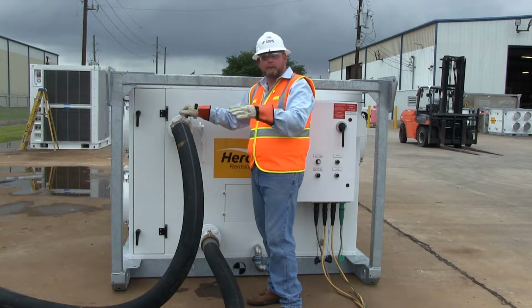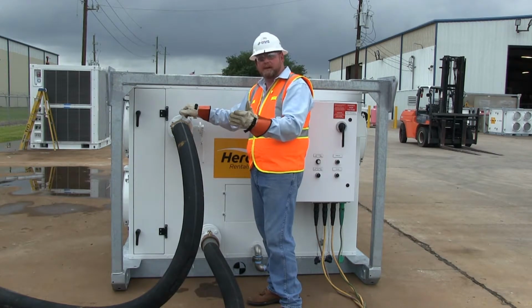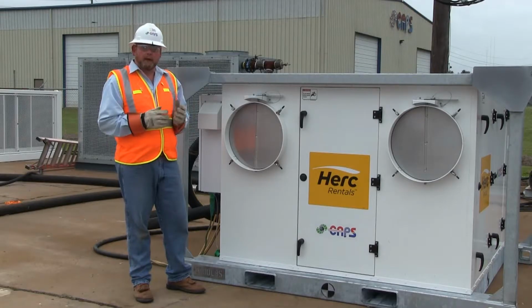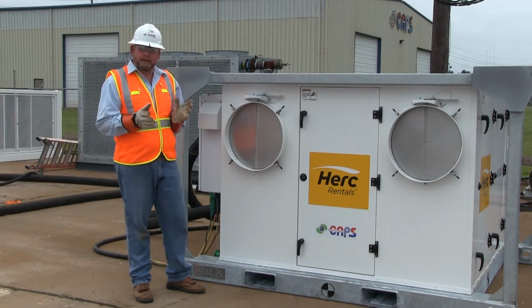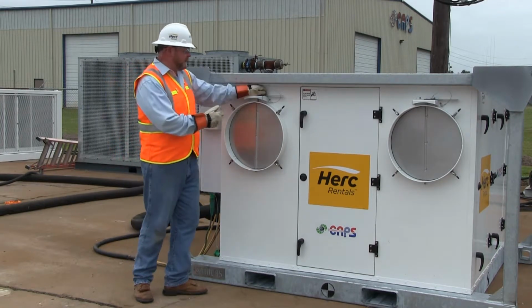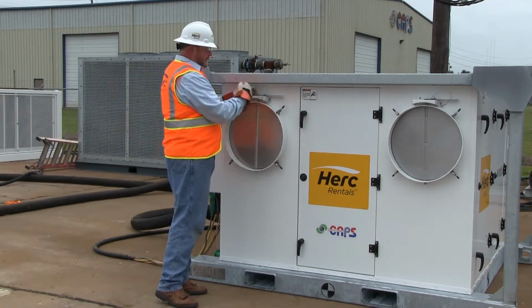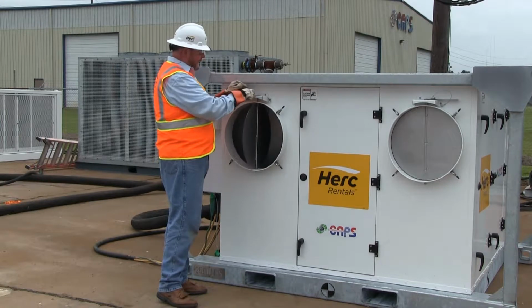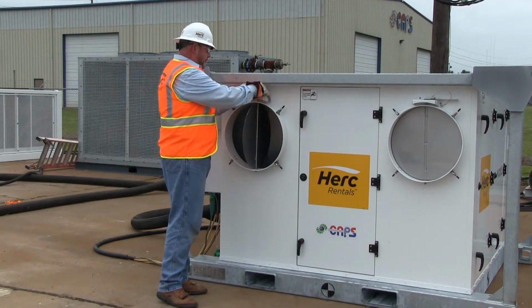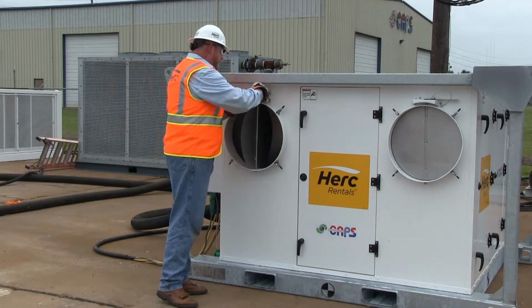Please note you can't operate a chill water system unless all the air is out of the system, because it's your heat transfer medium. Okay, our next step is going to be to hook up the supply air duct. On the 50-ton air handler, you're going to pull the stainless pins, open up the quadrant damper to 100% open, and you can drop the pin back into the hole.